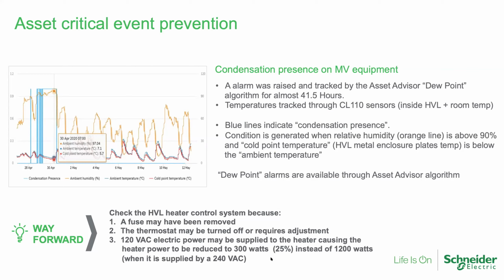The difference between that and analytics is that we have an analytical tool that can actually detect the dew point. This dew point calculation tells us when condensation occurs, or how far we are in time from having condensation present inside the equipment. This is relevant because water and electricity don't mix well. So after monitoring the behavior of humidity and temperature inside the HVL switch, we can determine the critical point to prevent a critical event.